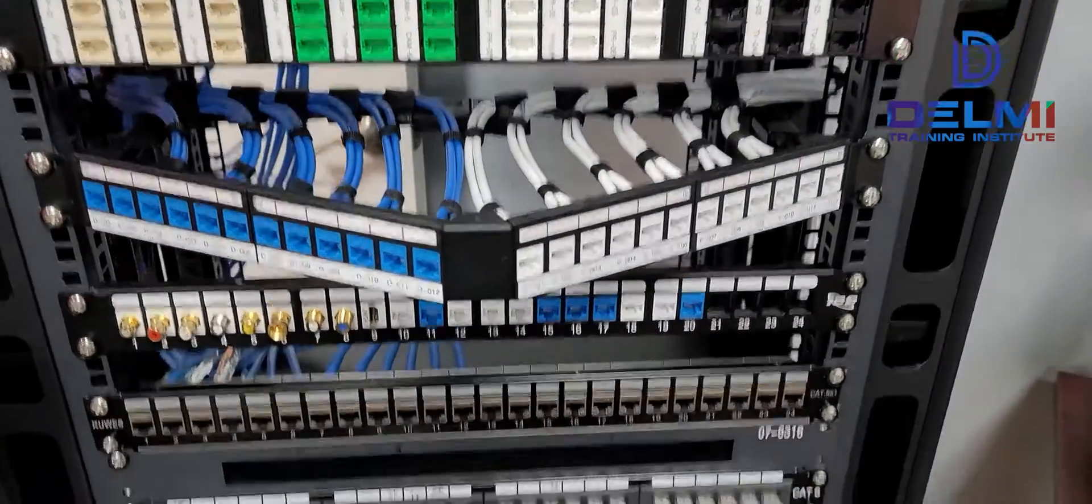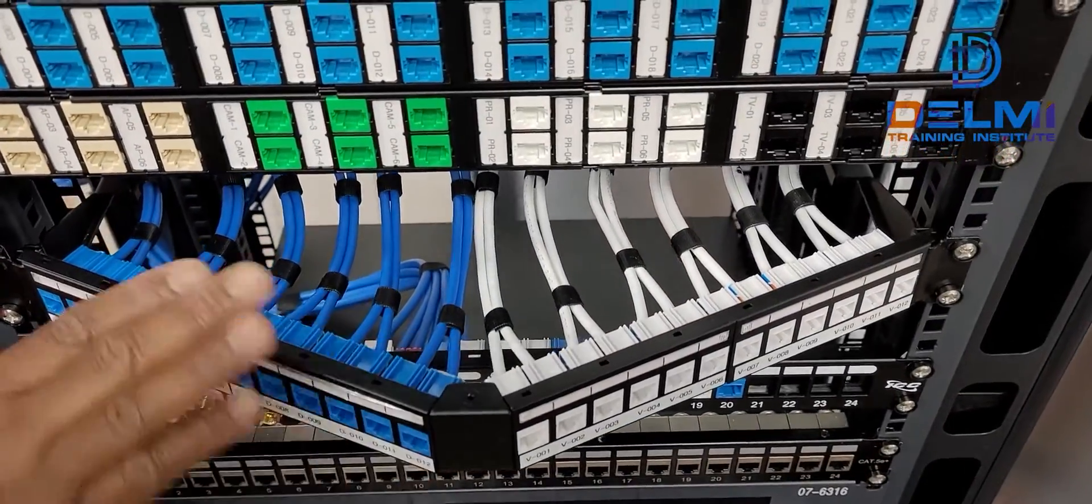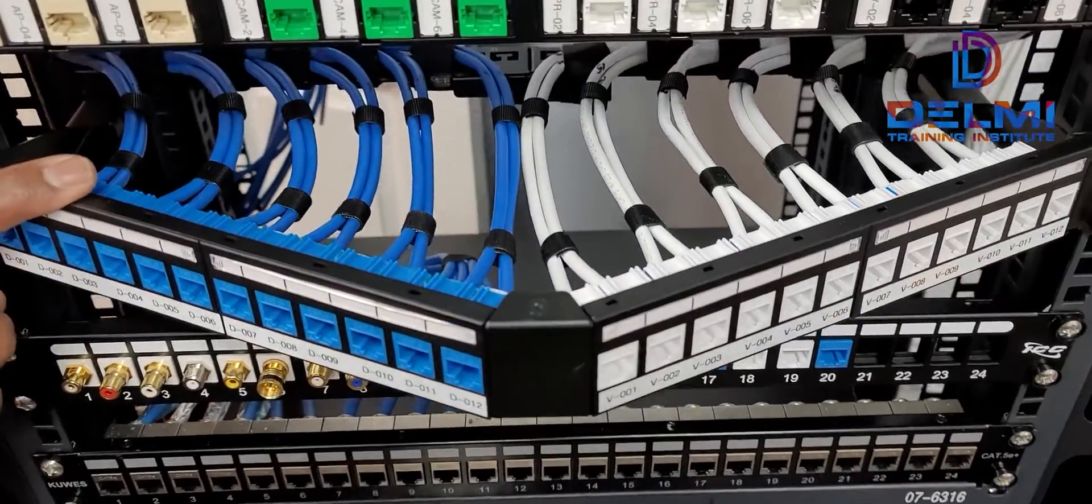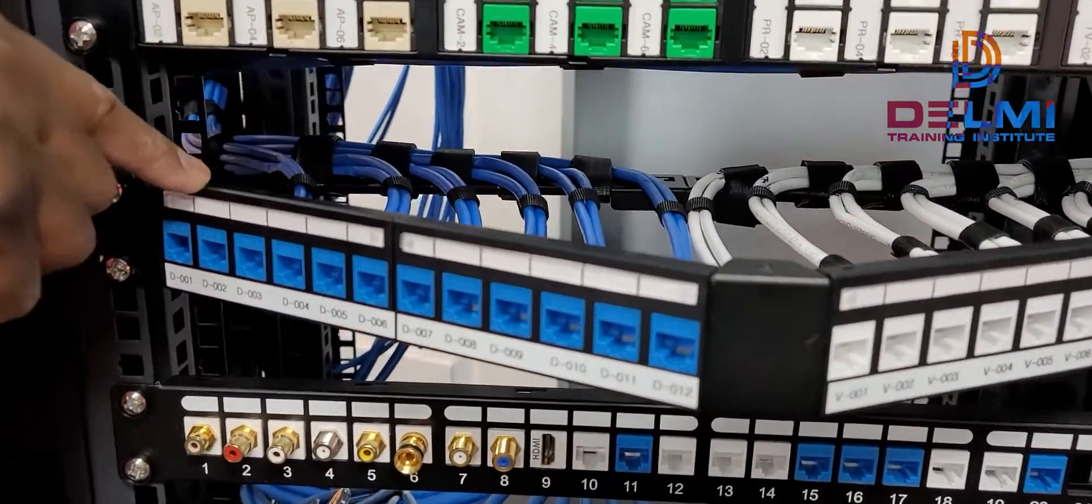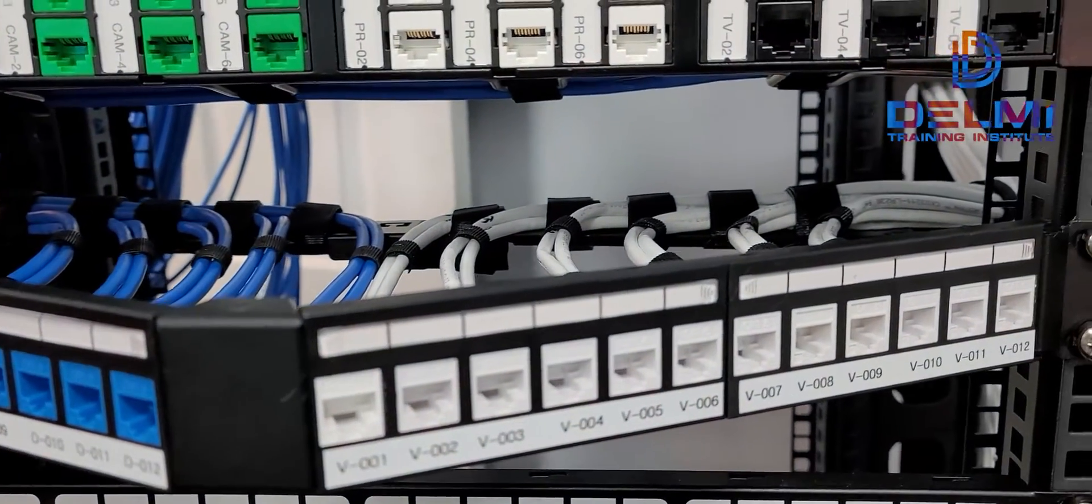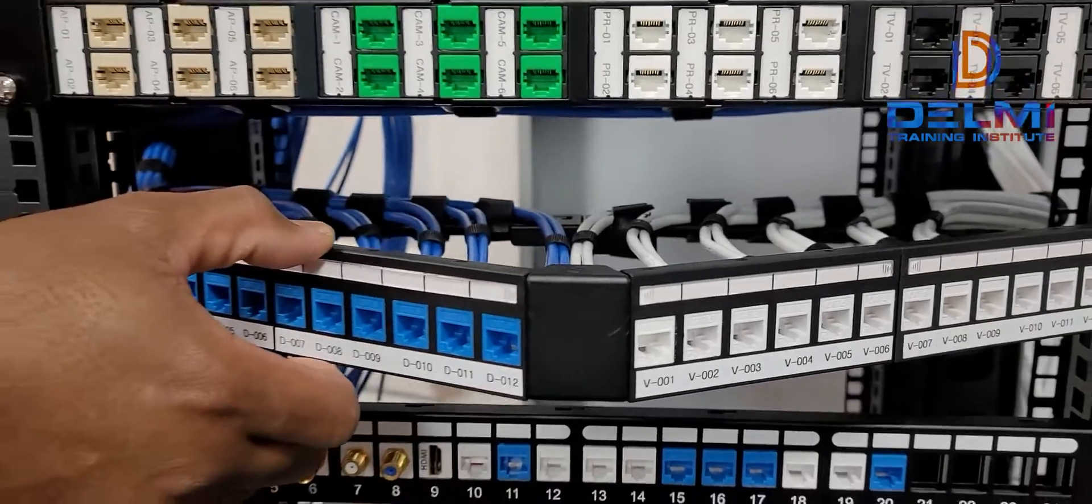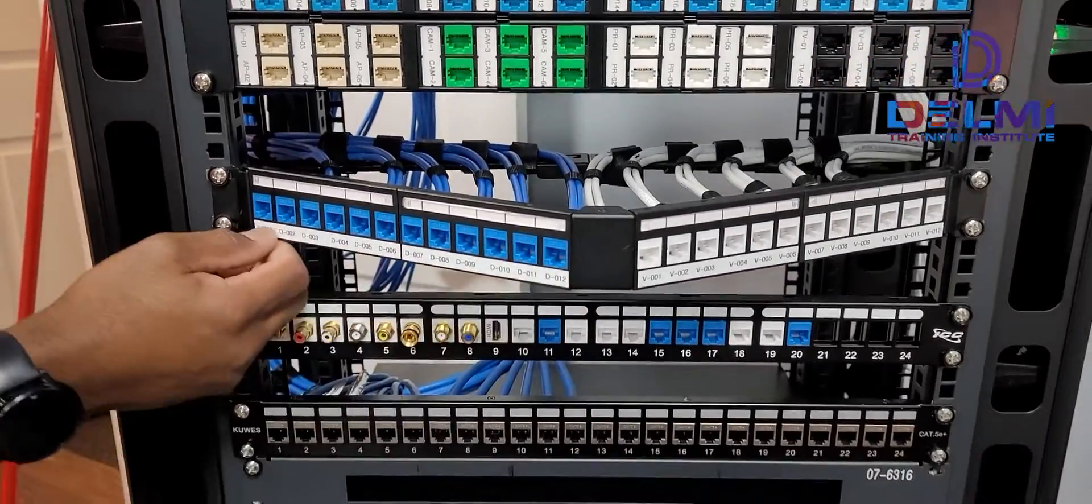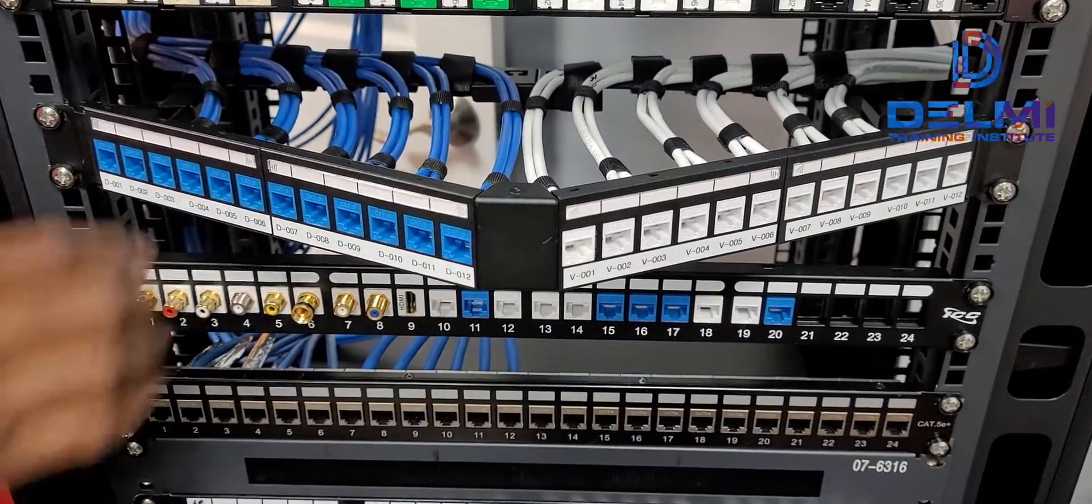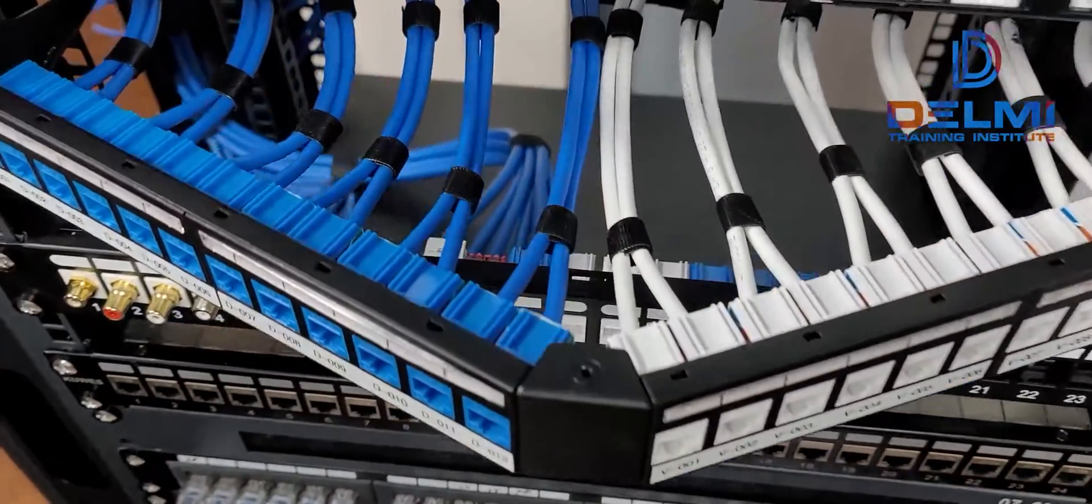The next one below is also a keystone patch panel which is unloaded but that has the angled form factor. It's just by preference. This is an angle and I decided to put my data on one side and my voice on the other side. Probably makes the cable management a bit cleaner. And that is how we terminate on these angled ones.